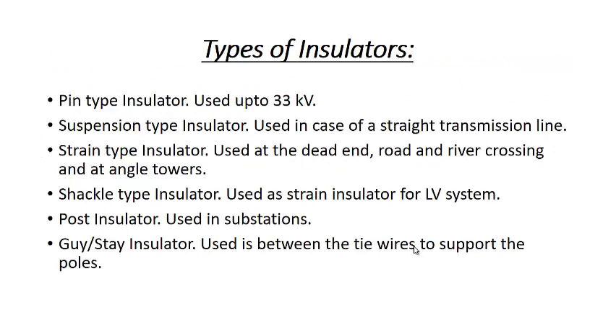Now let us come to the types of insulator. We have pin type insulator, suspension type insulator, strain type insulator, shackle type insulator, post insulator, and guy or stay insulator. This pin type insulator is usually used for 11 to 33 kV, or even lower voltage levels as well, because beyond 33 kV it will be very costly. And there are other drawbacks for pin type insulator as compared to these other types of insulators.